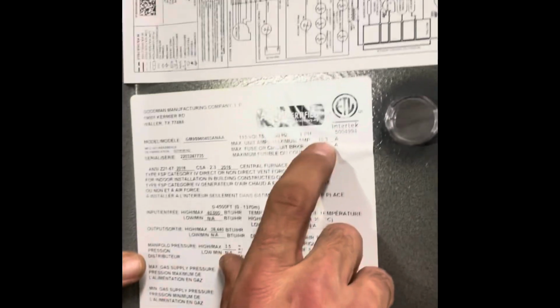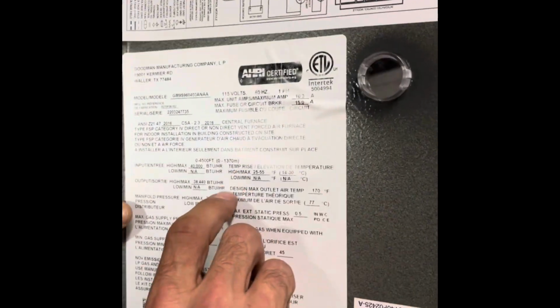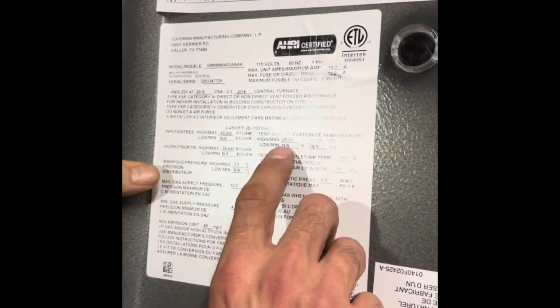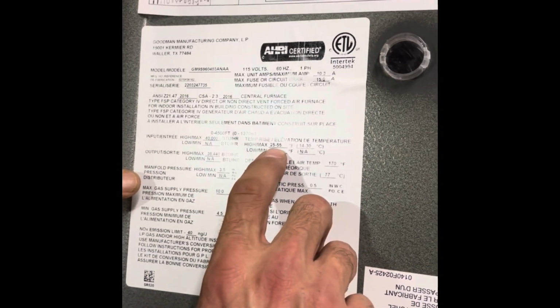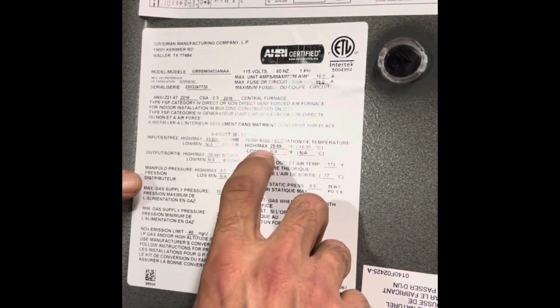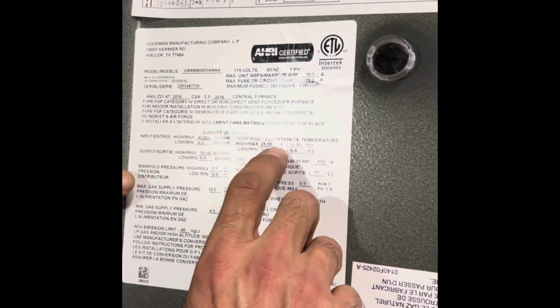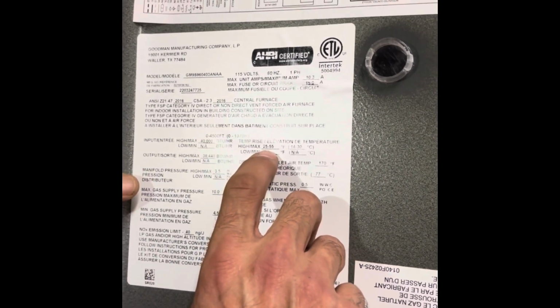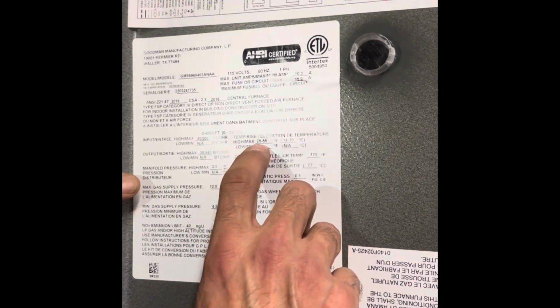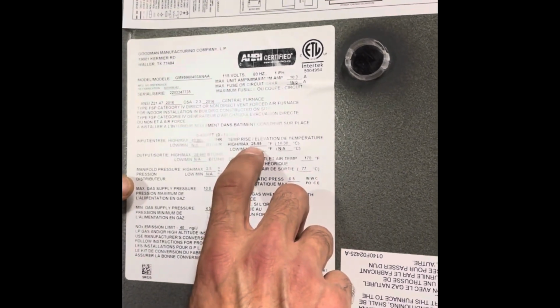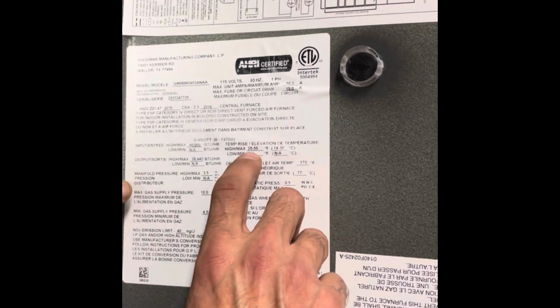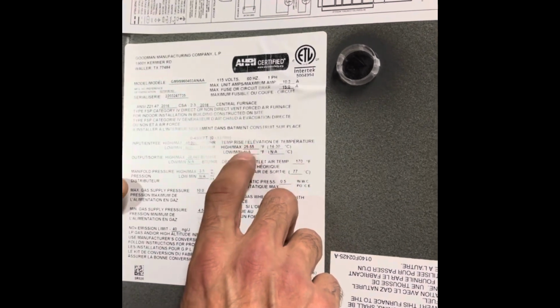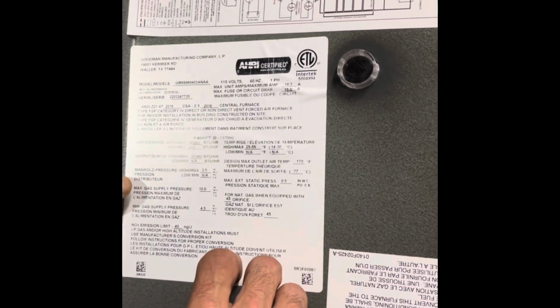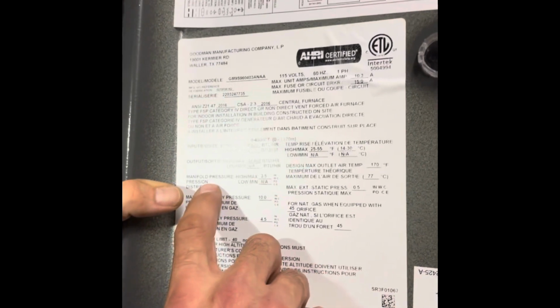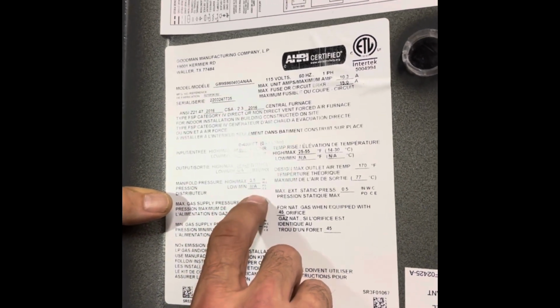So up here we've got a maximum unit amp draw of 10.3. We've got some temperature differences, so 25 to 55, this is called our temperature rise. That's the number we want to see, the difference between our supply air temperature reading as well as the returning air. So I will put a couple thermometers in the ductwork and we'll confirm that we're getting that number where it should be. If we go down here, we've got manifold pressure 3.5.